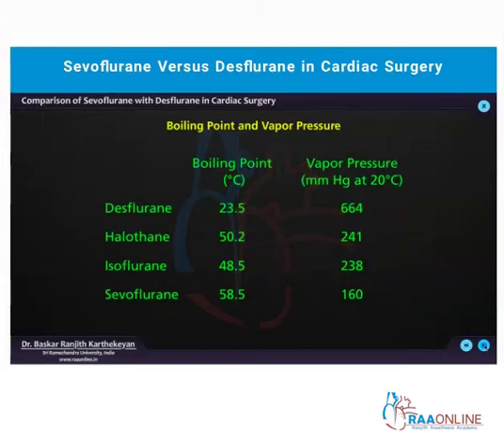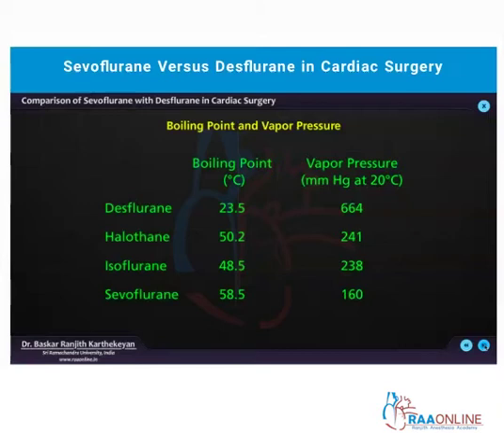Let us look at the physical properties of the halogenated volatile anesthetics. With regard to the boiling point, desflurane has the lowest at 23.5°C, and the vapor pressure at 20 degrees Celsius is 664, which is quite high. That is the reason you have a specially designed vaporizer for desflurane which needs to be electrically or electronically heated before use, unlike sevoflurane or isoflurane which can be switched on immediately and are ready for use.